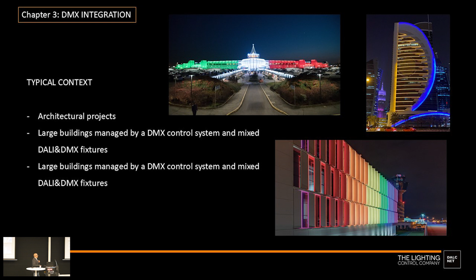As we said, there's a big difference in speed, and this can be quite limiting, especially when controlling dynamic lights like we usually do with DMX RGB control, because a DT8 RGBW signal on the DALI side can take something like 200 or 300 milliseconds to change one color on one luminaire. So making a dynamic effect on DALI is way more complicated than doing it in DMX.